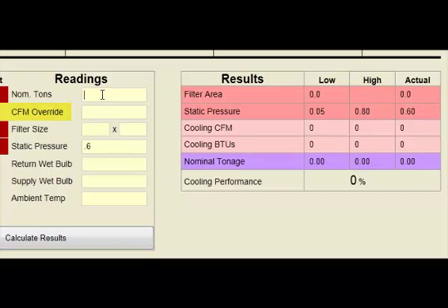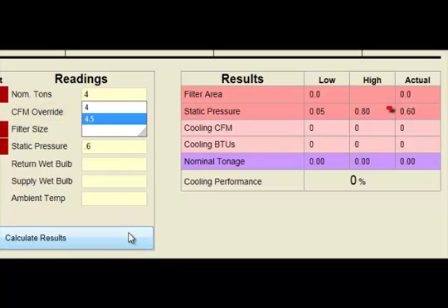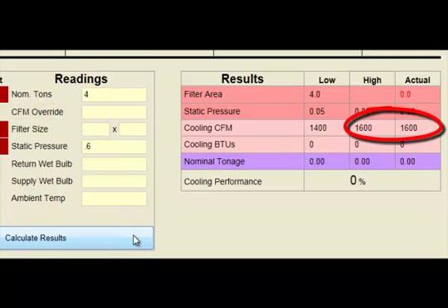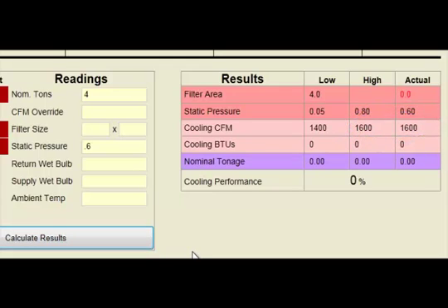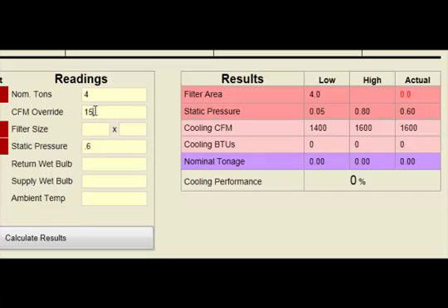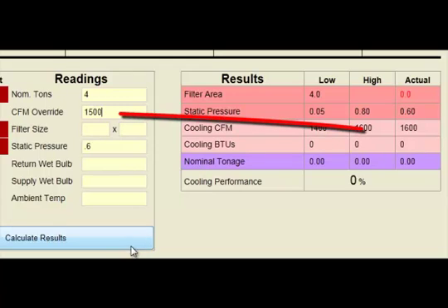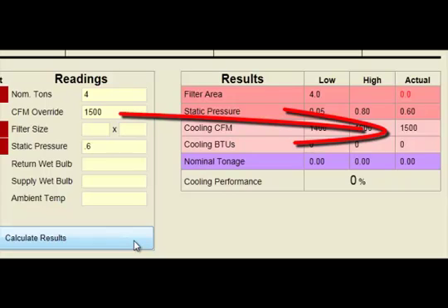The Cooling CFM Actual field initially defaults to the maximum cooling CFM reading and uses this number to initially calculate cooling BTUs and cooling performance. Total Performance Diagnostic uses the CFM Override field to change the actual default cooling CFM when better CFM information is available.